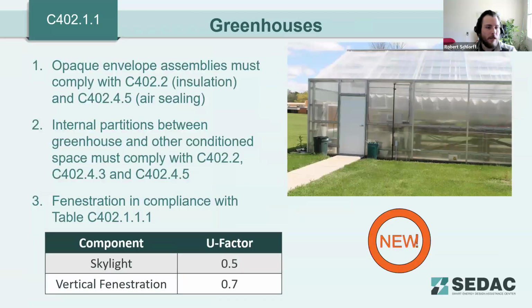Moving on. Okay, greenhouses. Greenhouses is a new section that's been included under the low energy buildings section within the 2021 code. Greenhouses are being called out as similar low energy spaces, but have their own specific requirements. These requirements are that the opaque envelope assemblies of that greenhouse, so if there's a rat wall below the fenestration or any other opaque portions of that greenhouse, must comply with C402.2, the exterior wall insulation tables, as well as C402.4.5, so air sealing.